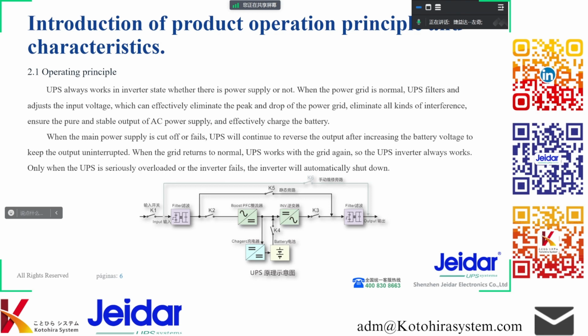When the main power supply is cut off or fails, UPS will continue to invert the output after boosting the battery voltage to keep the output uninterrupted. When the grid returns to normal, UPS works with the grid again, so the UPS inverter always works. Only when the UPS is seriously overloaded or the inverter fails, the inverter will automatically shut down.